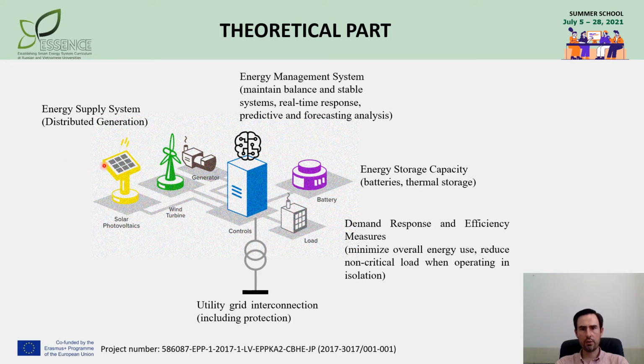The microgrid consists of the following main components: energy generating sources that are represented by a variety of different technologies. The main feature is that a primary source of energy shall be locally available. Controlled loads, whose consumption level can be adjusted in respect of demand response programs or energy efficiency measures when necessary. Energy storage, which is necessary in case of non-continuous availability of generating resources, and an energy management system, whose task is to collect the information from all actors and establish reliable and optimal operation as an integral object. So corresponding information channels shall be established in respect to the control strategy, which can be centralized, decentralized, or distributed.